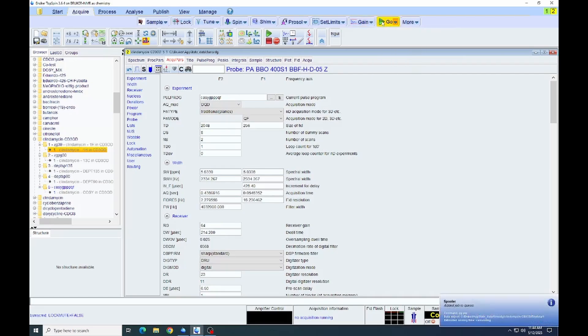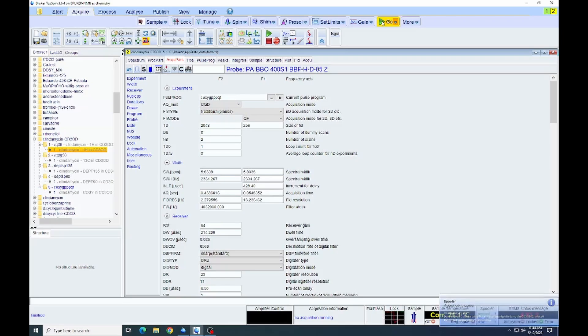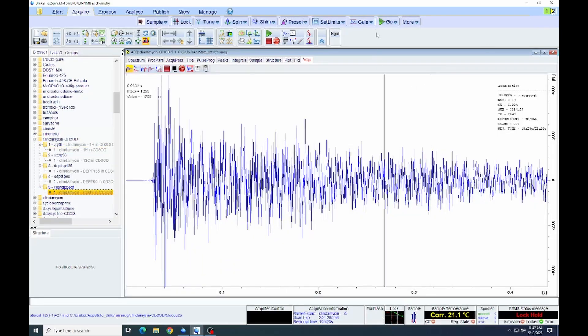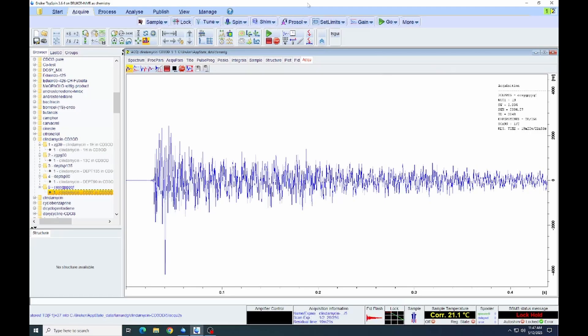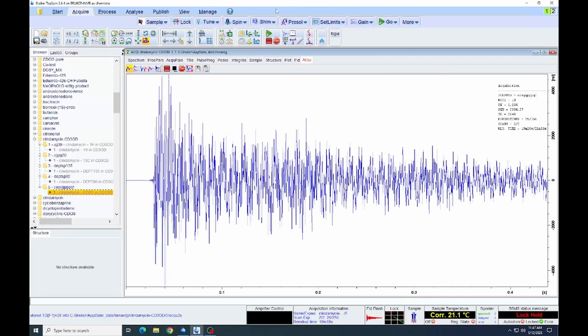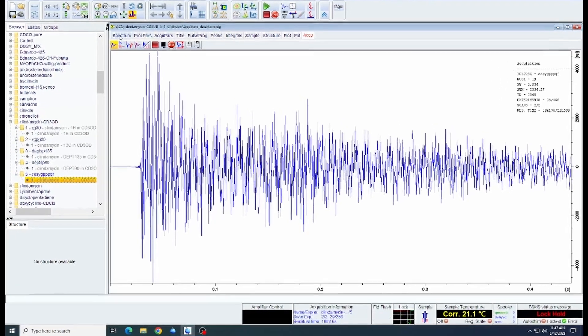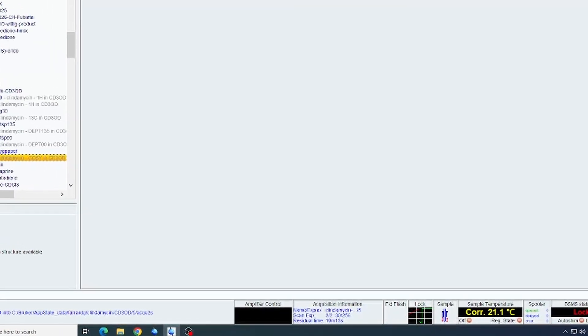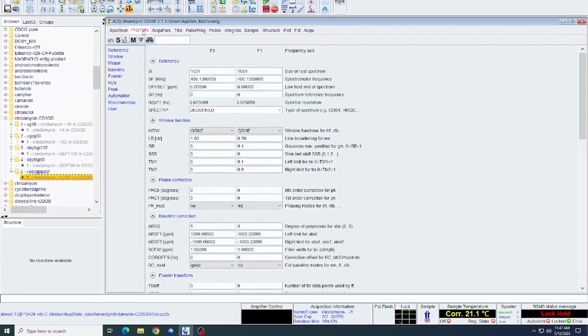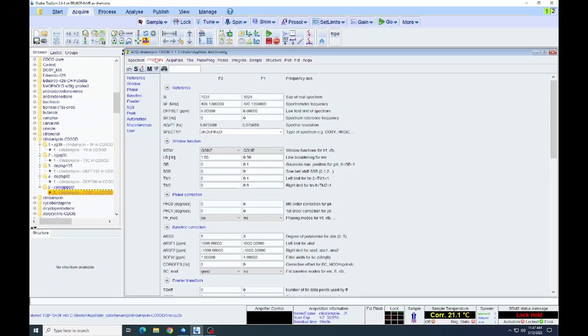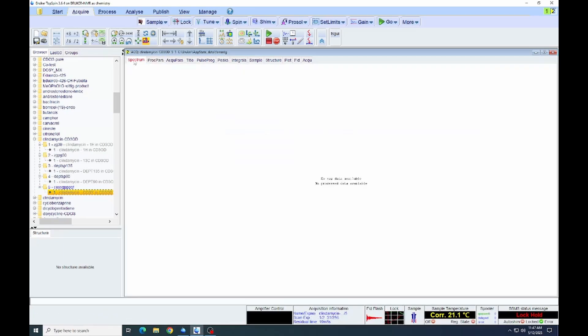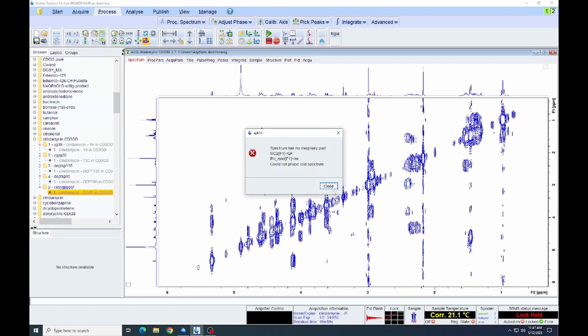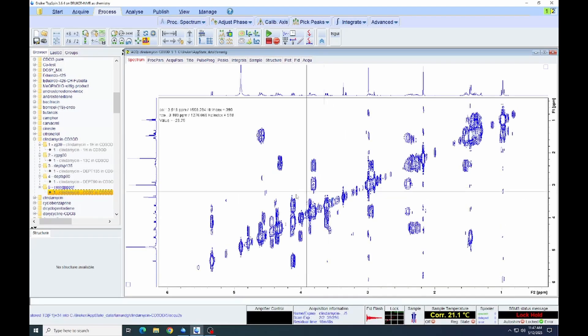We're not going to watch for the entire acquisition. I will show partway through. We'll come back and look at the status of the acquisition partway through to determine whether or not we want to continue with that. At this point, we can see in the window down here at the bottom of the screen that we've acquired around 30 scans so far. We can decide to process this the way we would just normally process the spectrum. We can click on the process button and the computer will process the spectrum, show us the result in the spectrum window or the spectrum tab.